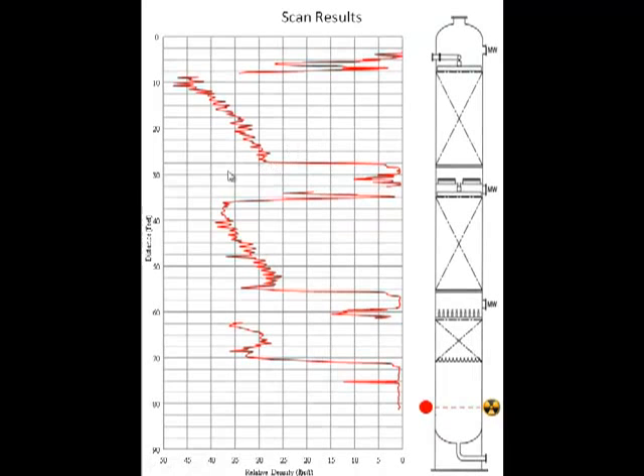In addition to that, the actual relative density readings are much higher than what would be expected for a column of this diameter and with this type of packing. So the first gamma scan essentially revealed that fouling was present through each of the three packed sections.